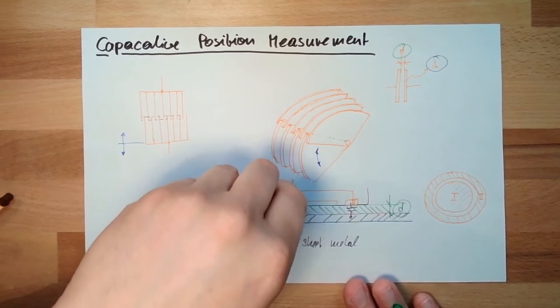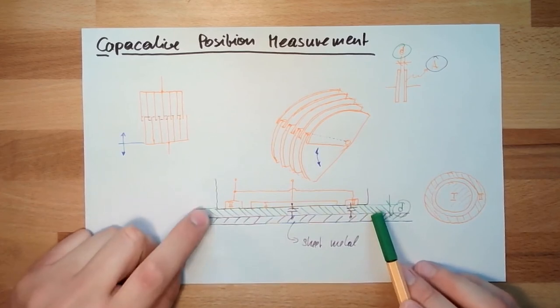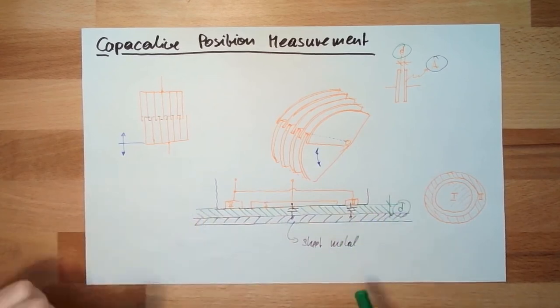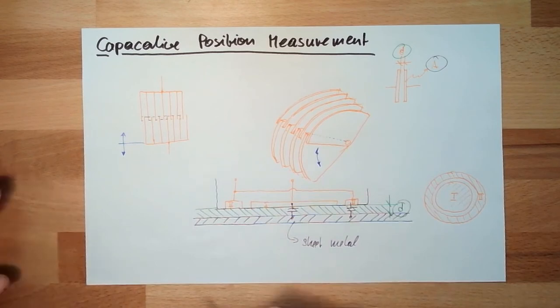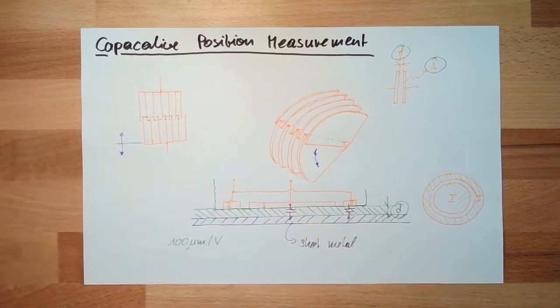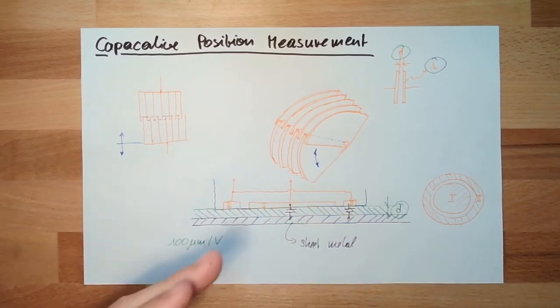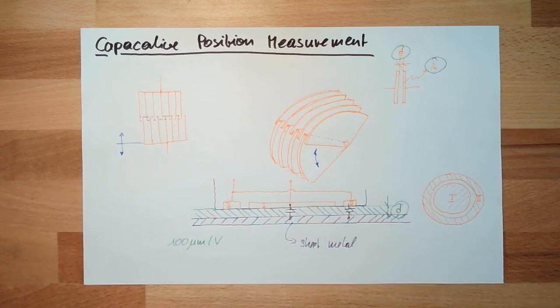There is some electronics measuring this distance. You can adjust the electrical properties of the coating material, of the isolating material here. You can adjust the sensitivity — a usual sensitivity is 100 micrometers per volt. Every time the distance changes 100 micrometers, the output will change one volt. This is used for instance for measuring the coating of a sheet metal — like the coating of your car. These sensors are usually working that way. Capacitive position measurement is typically used for small, small changes.